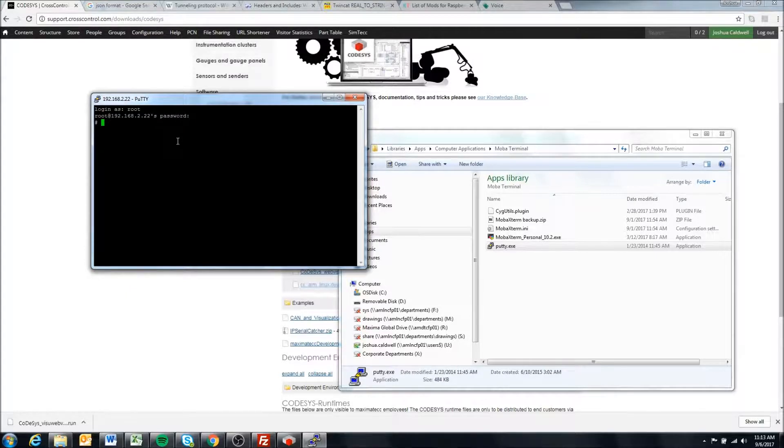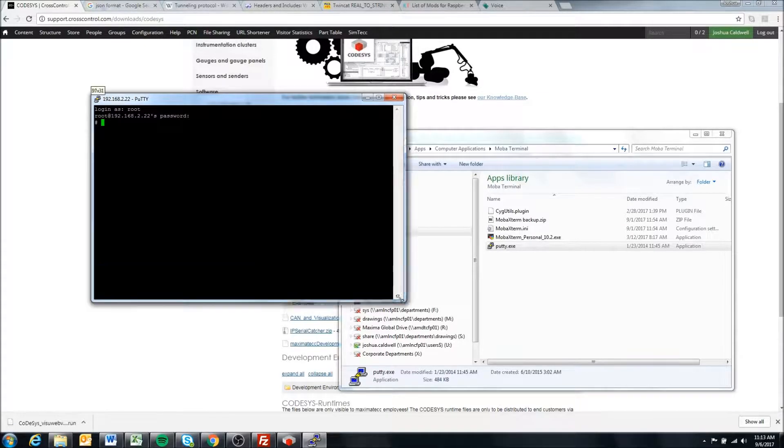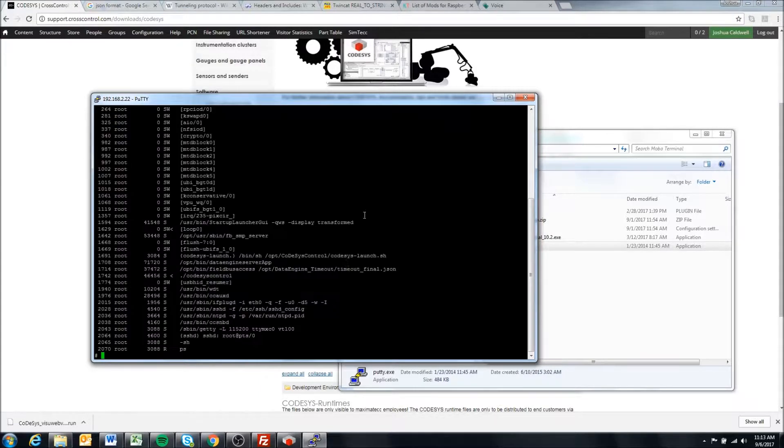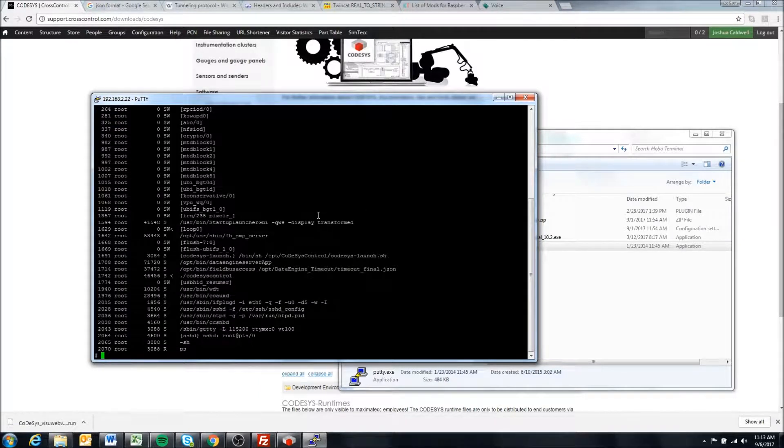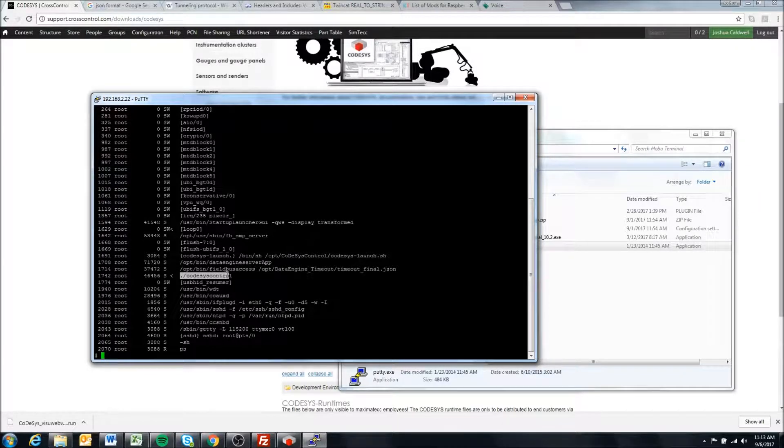Now that it's rebooted, we're just going to check to make sure the Codesys runtime is running. I've gone over this in the troubleshooting connections video, but we're going to type ps. We just want to make sure that we see this codesyscontrol, so that means that the runtime has started on the device.